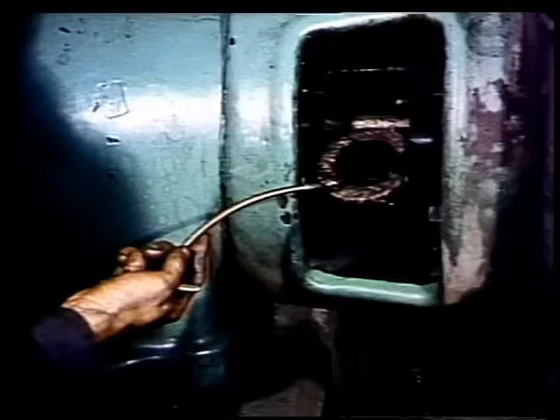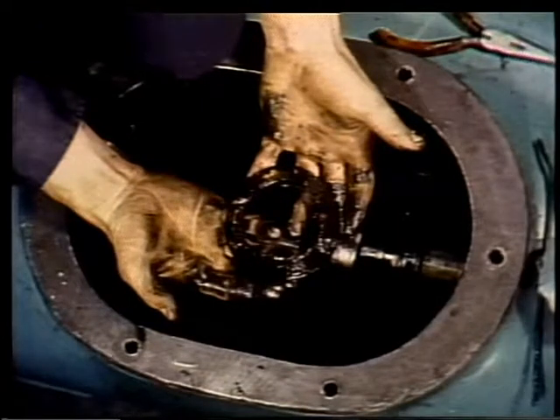Next, you remove the packing and oil wipers. This should be done before the piston rod is pulled. Otherwise, the threads on the rod could be damaged.